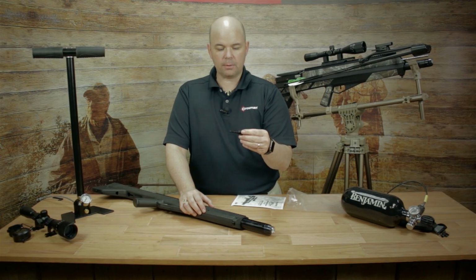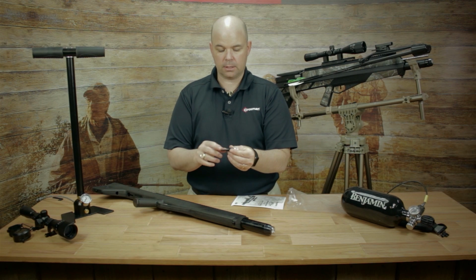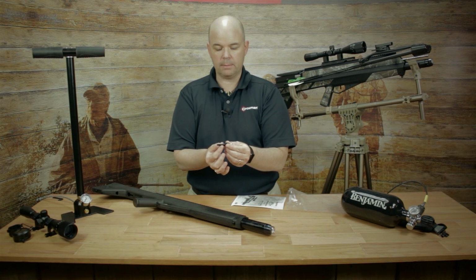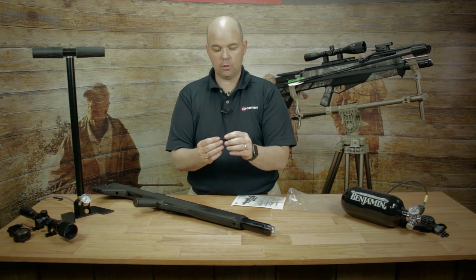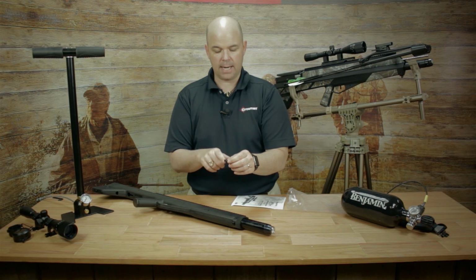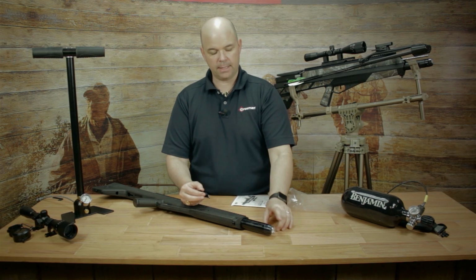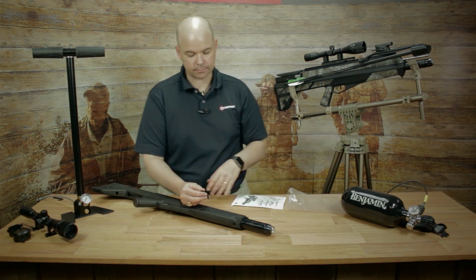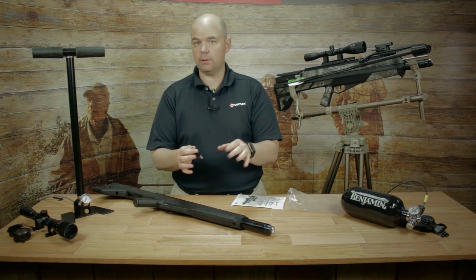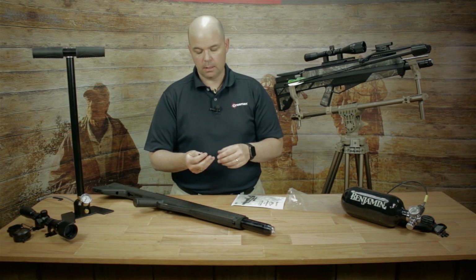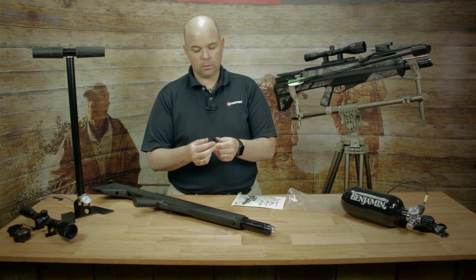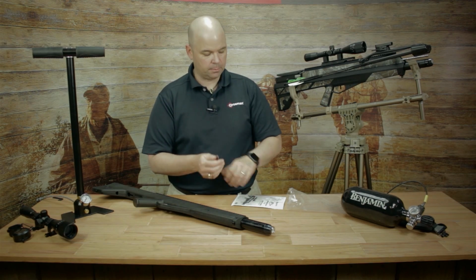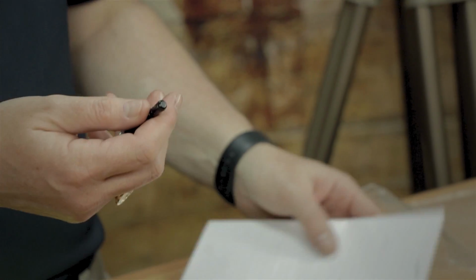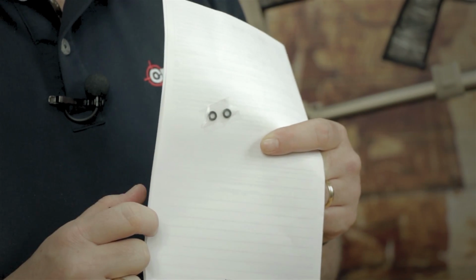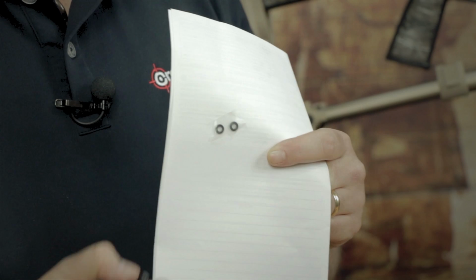If you improperly insert it, you risk clipping or rolling back these O-rings. These O-rings create a seal on either side of the hole in the probe, which matches up with a hole in the reservoir. But that's okay. If you do happen to make the mistake of clipping or rolling back an O-ring, you can either roll it back into place, or if you clip it or break it off, there are 2 extra O-rings taped to the back of your owner's manual, and you're welcome.